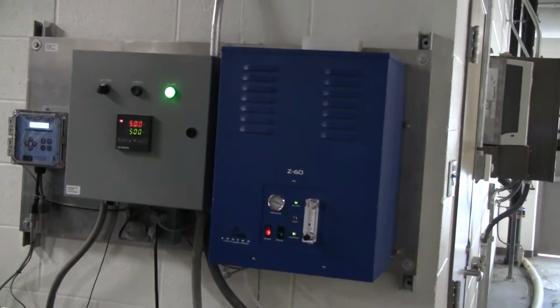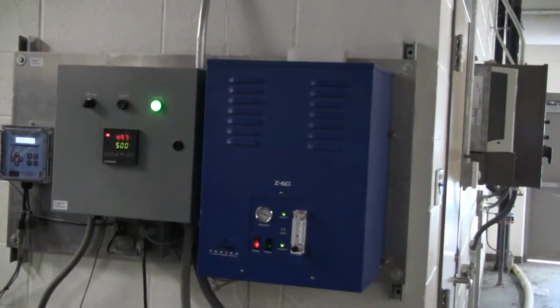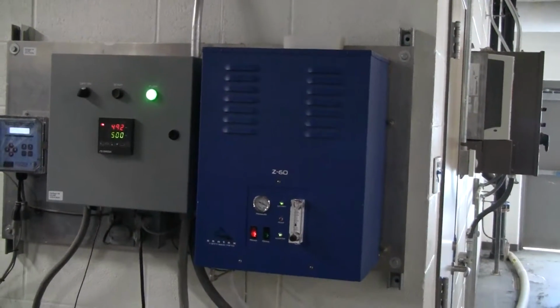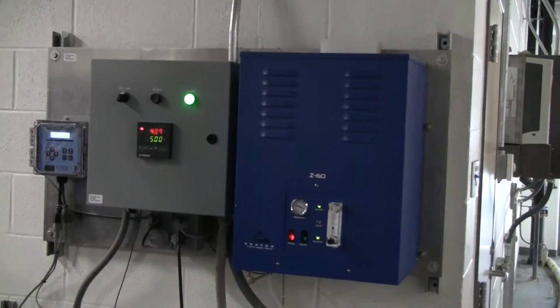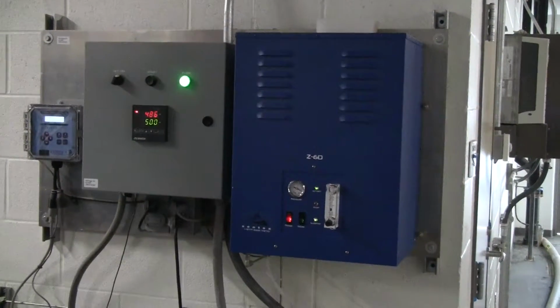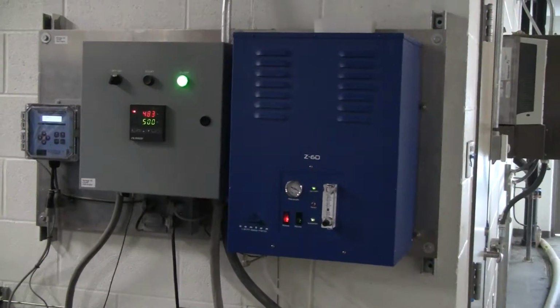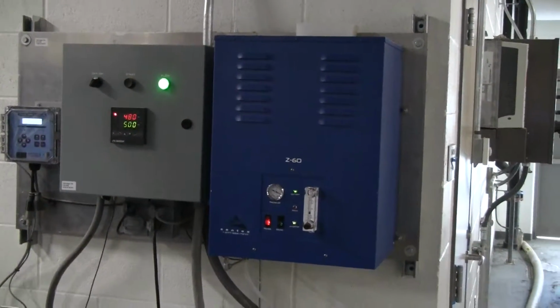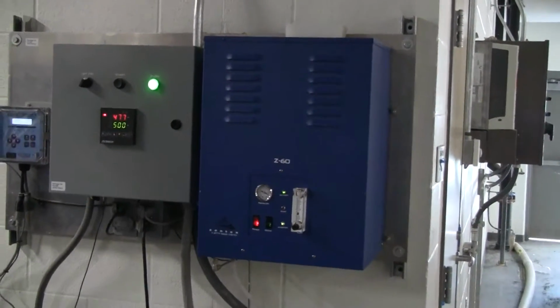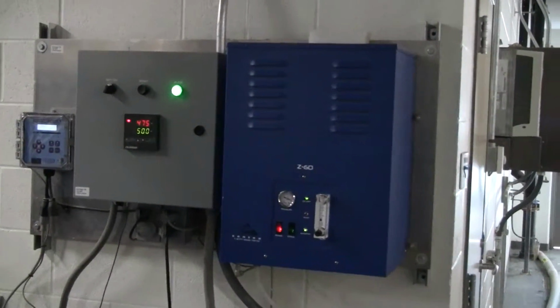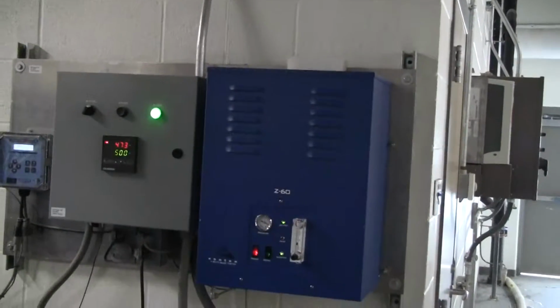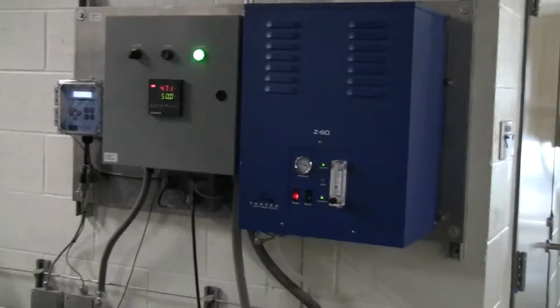So in times of high load, as you can see, we're dropping below set point right now and starting to kick in. During times of high load, we generate enough ozone to kill all the bacteria and destroy all the organics, while during low load periods, we're minimizing the amount of ozone generated to protect the system from corrosion. That is the gas side.